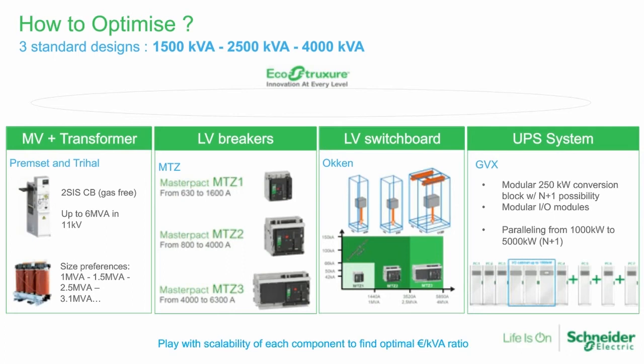For instance, we also optimized the short circuit impedance of the transformer with an additional 1 or 2%, in order to have the right form factor and the right size and range of small breakers downstream, to be able to have the right cost optimization at the end of the day, not compromising the continuity of service and the protection coordination.